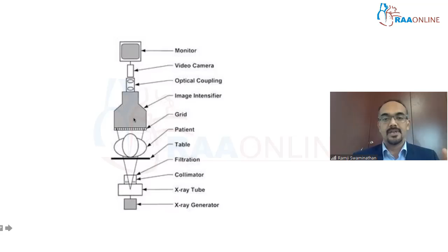The patient lies on the table and the X-rays pass to the patient, and I will subsequently be discussing the scattering of X-rays. But prior to that, this is the simple physics or mechanism behind the use of a fluoroscope in our clinical practice. X-rays get emitted from the X-ray generator, pass through the collimator, pass through the patient, and ultimately reach the image intensifier. As you can see here, this is the image intensifier, the recording part of the fluoroscope. This is where the X-rays that come out of the patient go and hit. The X-rays that hit the image intensifier are converted into a visible image. This visible image in turn is captured by a video camera and subsequently displayed on a monitor. So this is, in simple terms, how a fluoroscope works.